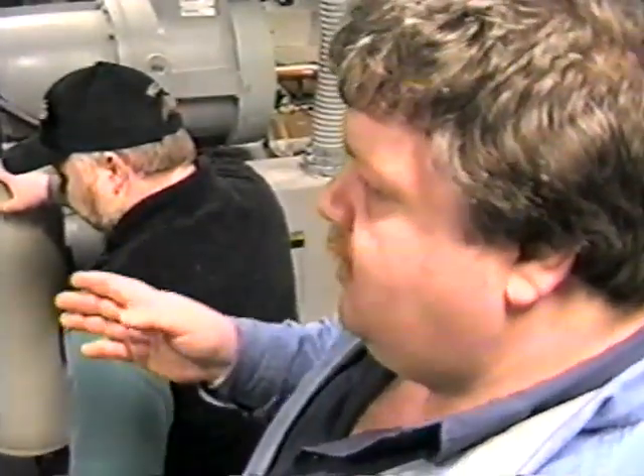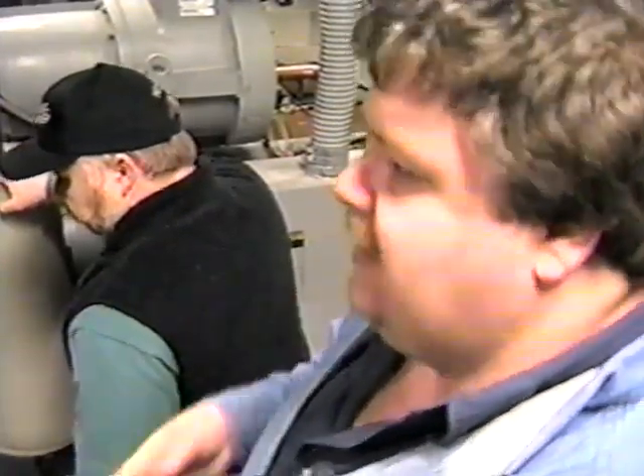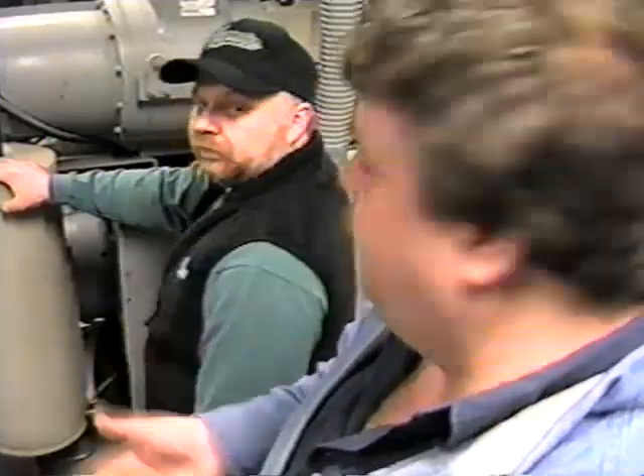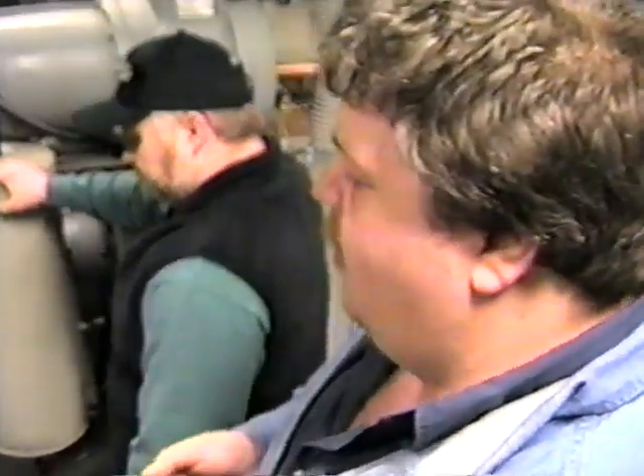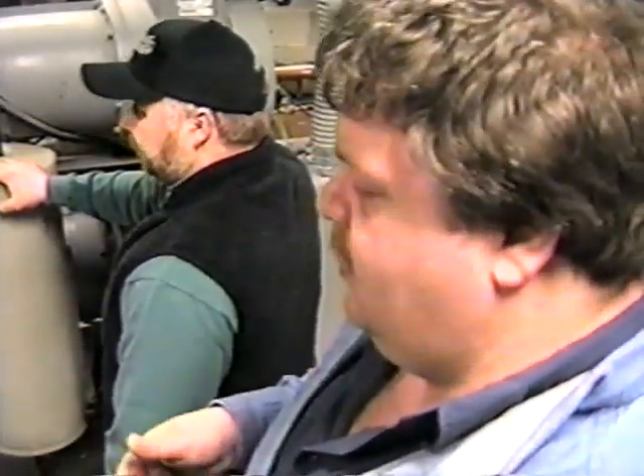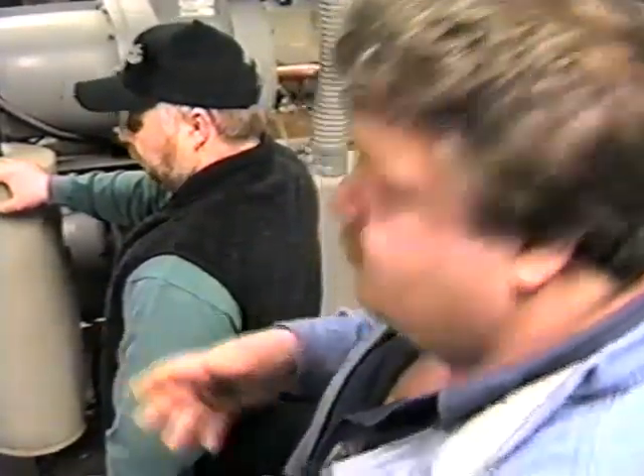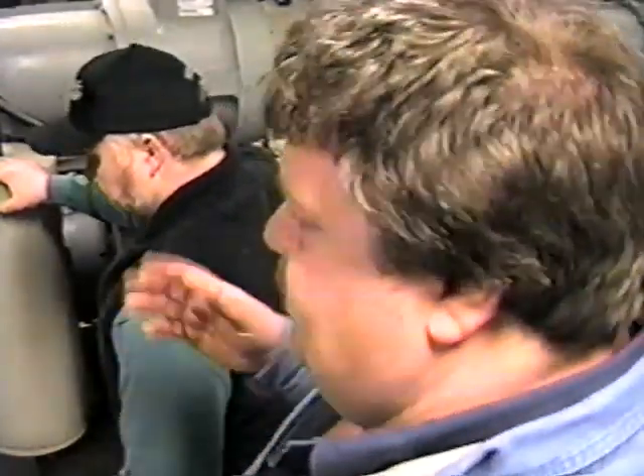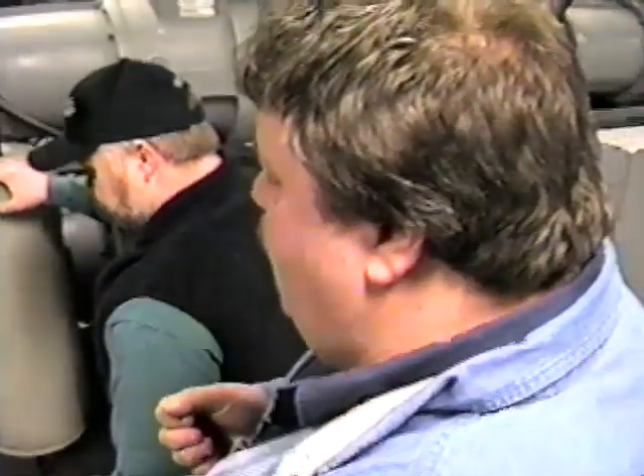The decreased speed of the pump also decreases the heat injected back into the system due to friction in the brine that you get with the pump running at high speed. So that means the compressors have to run less often. All right, so we're basically saving all the way around there.